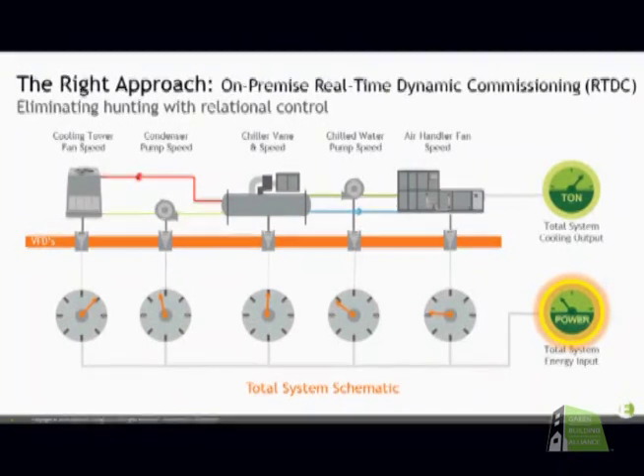But a good way to think about it is if you were going to have an additional 10 kilowatts of power, wherever that's coming from, you're generating it from a solar panel, or it's coming in somehow more cheaply than you would normally get it. Where would you apply that in the system to get the same amount of cooling, or to maximize your amount of cooling? I know a lot of operators who look at, well, the chiller uses the most power, so you want to focus on increasing the power of the chiller when you increase the amount of cooling. But really you need to see what everything is doing in concert, because you might be using more energy than you need to at the chiller, and you're just able to speed up your cooling tower fans in order to reject that heat and gain system efficiency, not just component efficiency.